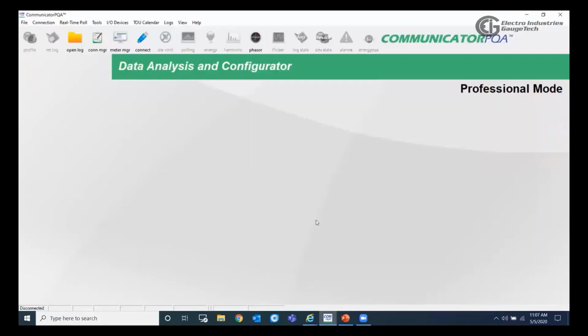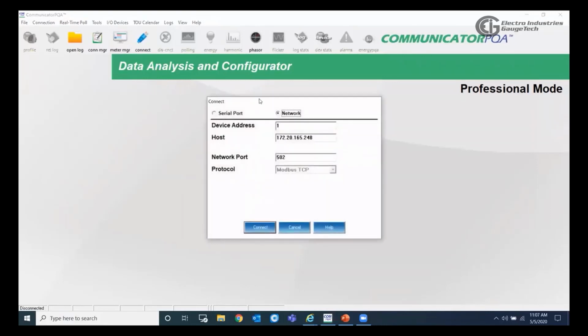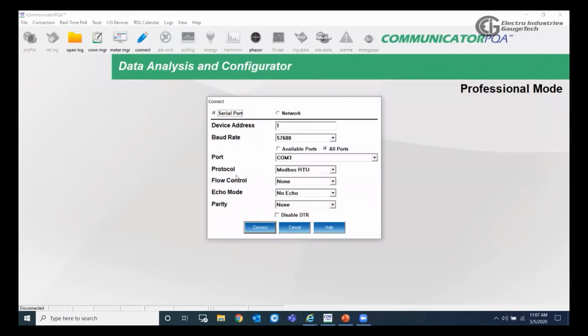So going back to the communicator, we would start by connecting with the meter. To do the connect, we have the connect icon here. I will click on this, and as you can see, we have 2 options. The serial port would be used when we are connecting to the Nexus 1450 using any of the serial ports, either the RS-232 or the RS-485. These settings should be matched with the port setting itself.